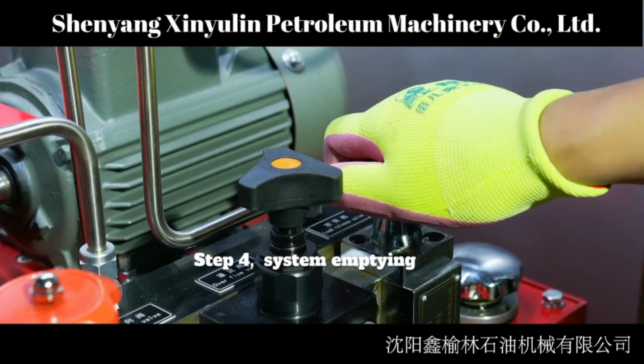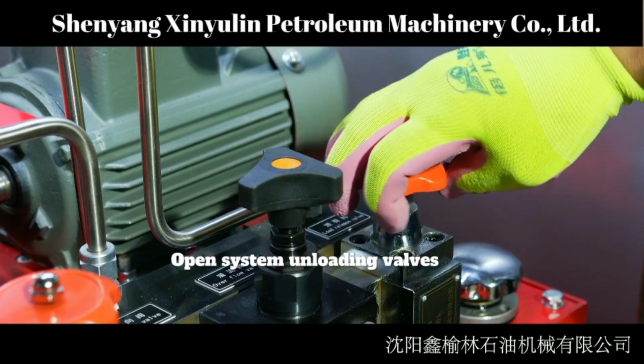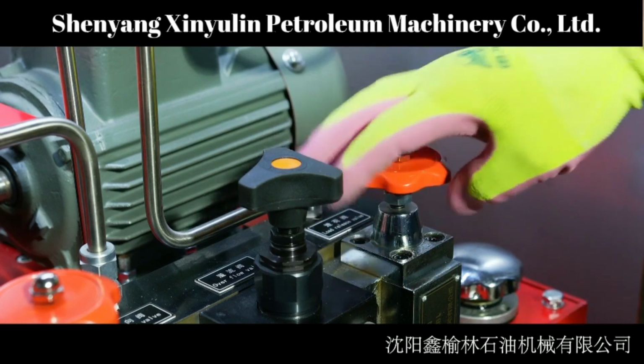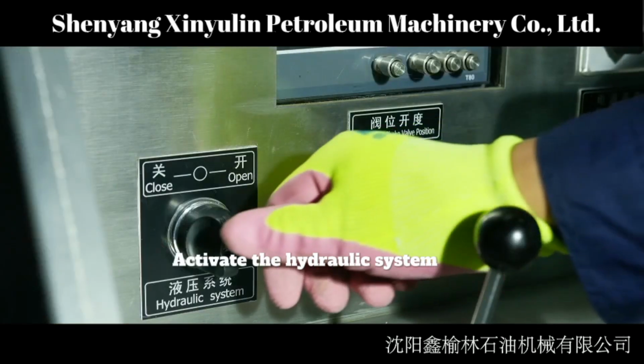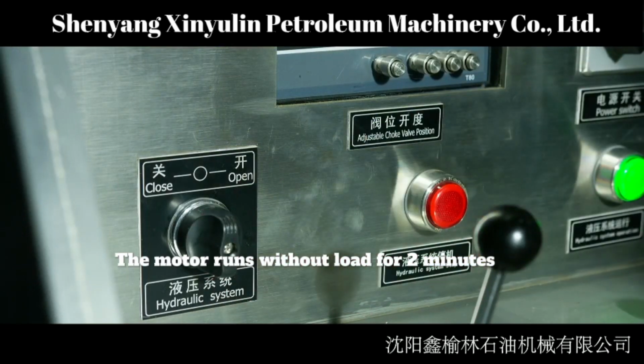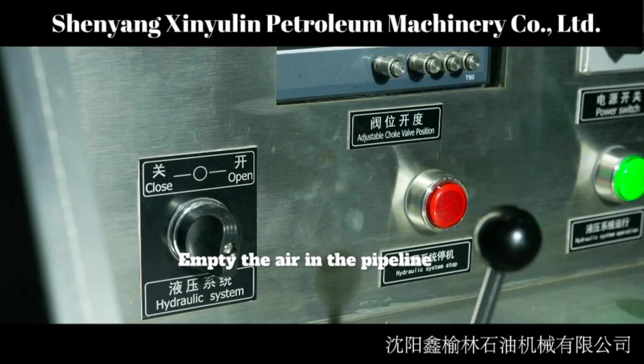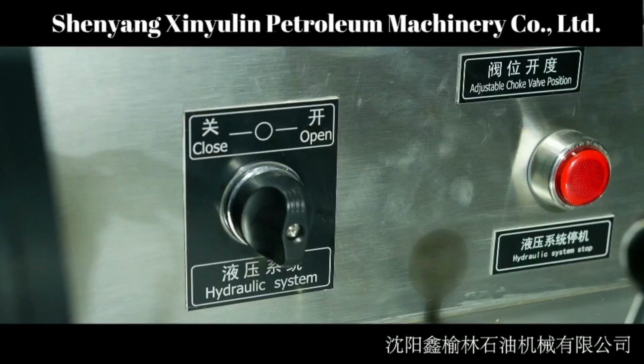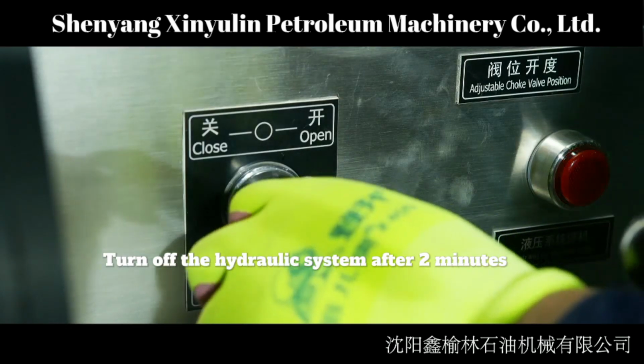Step 4. System emptying. Open the system unloading valve. Activate the hydraulic system. The motor runs without load for 2 minutes. Empty the air in the pipeline. Turn off the hydraulic system after 2 minutes.